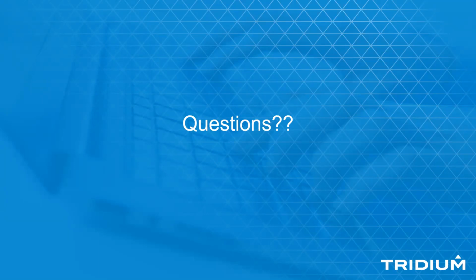Charles McLuhan is asking, can you use this with an LDAP server? Yes. If you have your supervisor set up to do LDAP, when your customer tries to log into one of the subordinate stations through single sign-on, they're going to be redirected to the supervisor, and then they will be able to log in to the supervisor with their LDAP account and then be redirected back to the station they were actually trying to log into. So, yes.